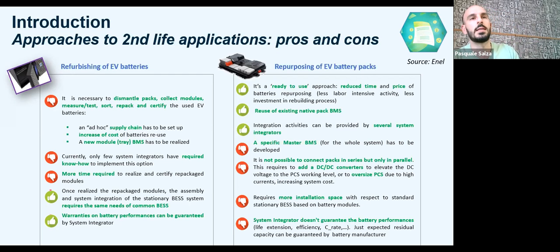Other limits are more technical: typically the voltage of the single packs is lower than what's used in stationary applications. From a certification standpoint, these packs aren't meant to be connected in series. So to reach the required voltage level, or to work with standard power converters and inverters, you either need to add DC-DC converters to match the pack voltages with the inverters, or use inverters that work at lower voltages, which is more expensive because for the same power, lower voltage means larger equipment.